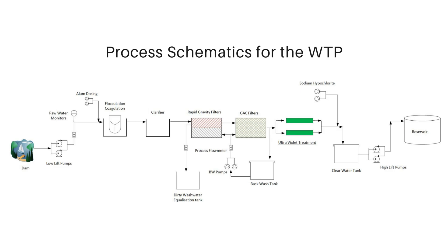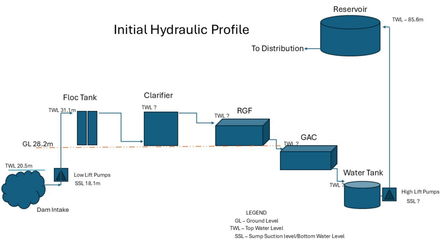With time the filters will become clogged because they collect all that dirt, so there is a need to clean them using a process called backwash. We pump water in the reverse direction — when a filter is working, water is introduced at the top, filters through the sand, and is collected at the bottom via nozzles or an under-drain. During backwash, water rises up through the nozzles or under-drain carrying all the dirt out. Backwash can also be done simultaneously using an air blower.